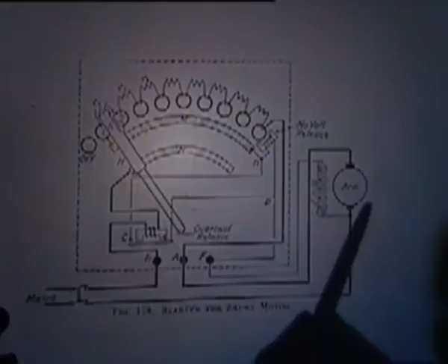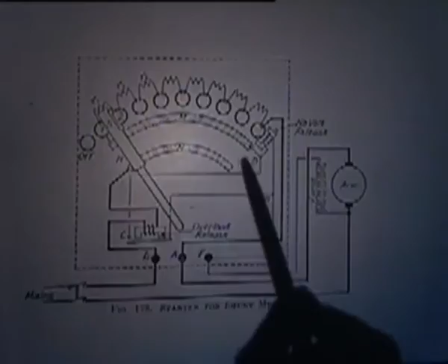Then the other way is another protection called a no volt release. That means if suddenly the voltage supply goes off, you don't want the handle to remain in this position, because the next time you want to start the motor, you would be starting with no resistance. So as soon as the switch is off, it should come back. With the no volt release, when there is no voltage across this, it gets automatically de-energized and comes back. It will also protect in case the field winding is not carrying any current, since it will de-energize when the field gets disconnected. So you have protection from this starter when there is no voltage, or when there is overload, or when the field is not excited. So this starter protects the DC motor against all these heavy odds.